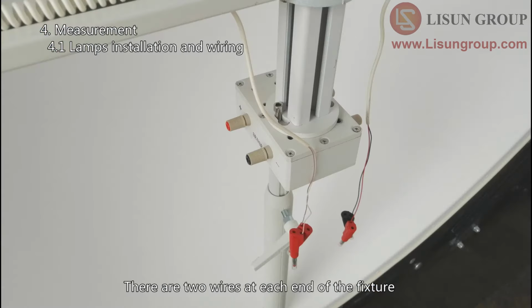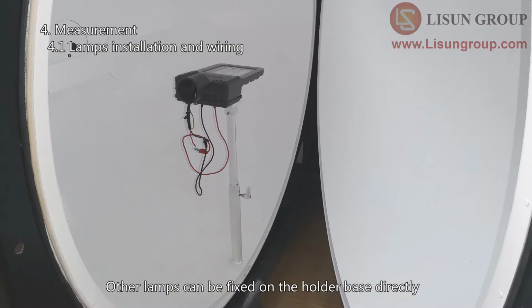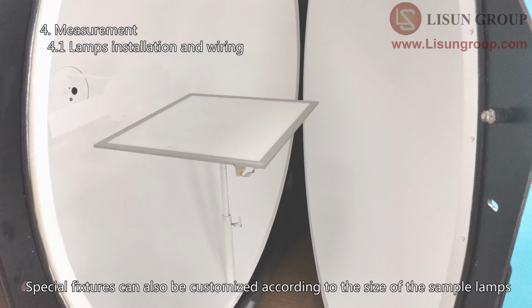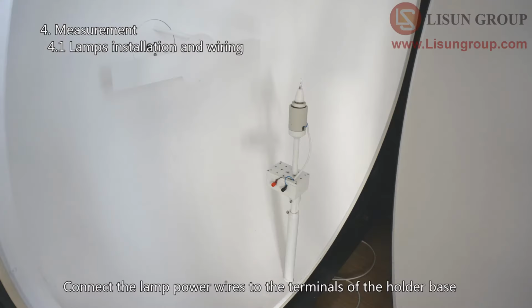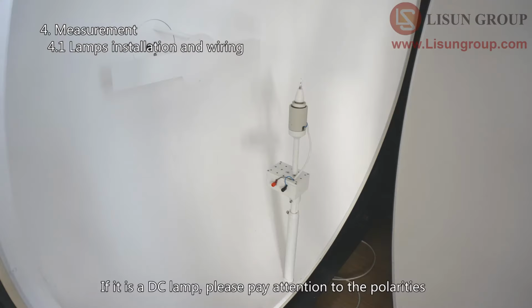There are 2 wires at each end of the fixture. Use the 2 wires of one end for single-ended lamp tubes. Use 1 wire of each end for double-ended lamp tubes. Other lamps can be fixed on the holder base directly. Special fixtures can also be customized according to the size of the sample lamps. Connect the lamp power wires to the terminals of the holder base. If it is a DC lamp, please pay attention to the polarities.